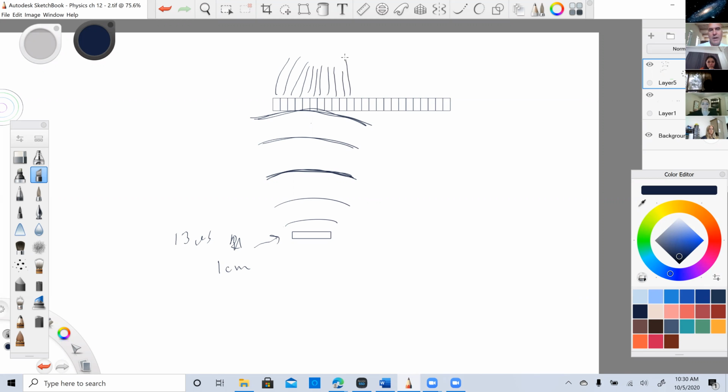All those wires are going to receive the echo. I'm sorry, the wires, and therefore each individual element, is going to receive that echo at just the slightest difference in time. And so it's actually going to create a curvature in the electric voltage that is created. Remember, these are piezoelectric. You push on them, it creates electricity. You add electricity, they vibrate, they create sound. So they work in both directions.